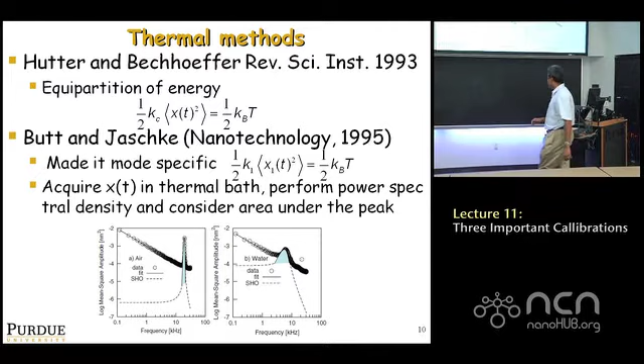Sometimes, how you calculate the area under the curve is an issue. If I give the same curve to each one of you, each of you will give me a different number for the area under the power spectrum. So there's an issue. What's the norm for it? How do you decide this? Okay. When you go to higher eigenmodes, you need to know the deflection of the cantilever, and that requires you to calibrate higher eigenmodes of the cantilever, which is not easy.